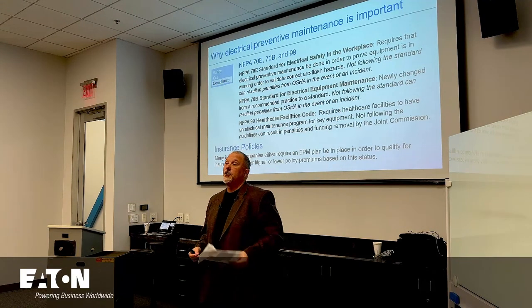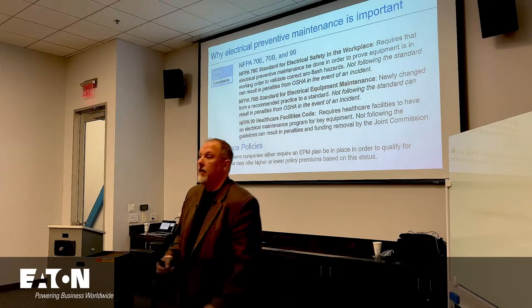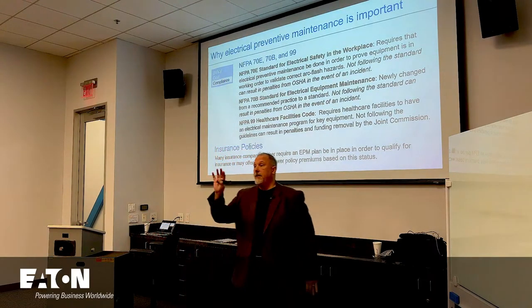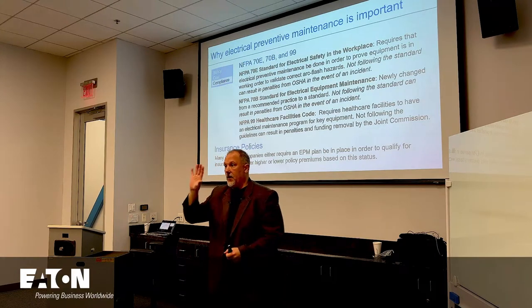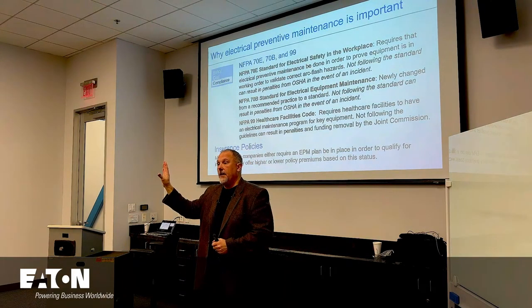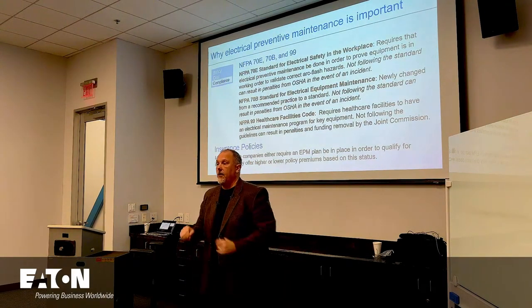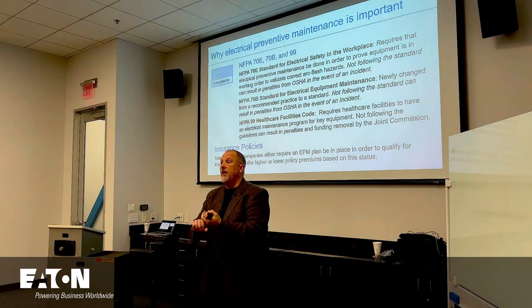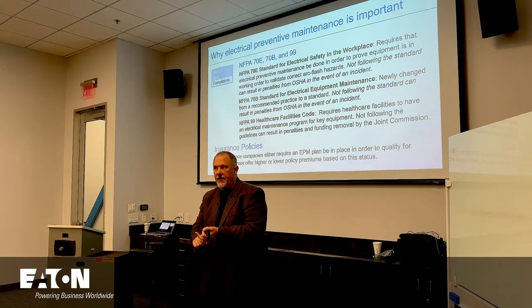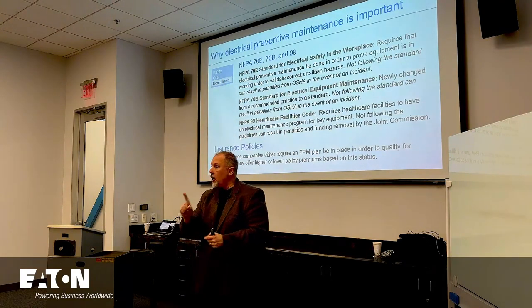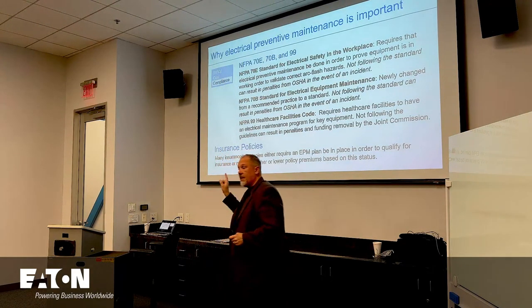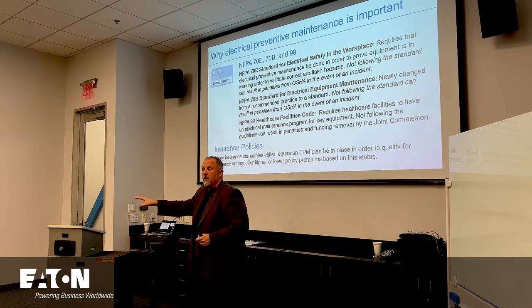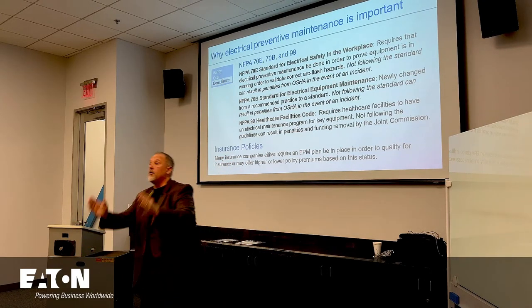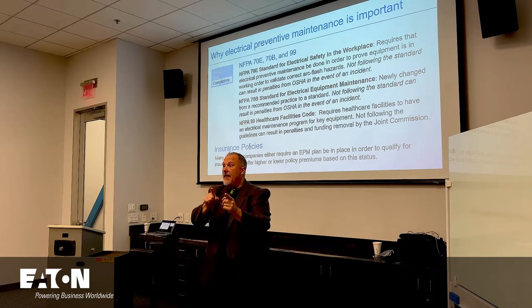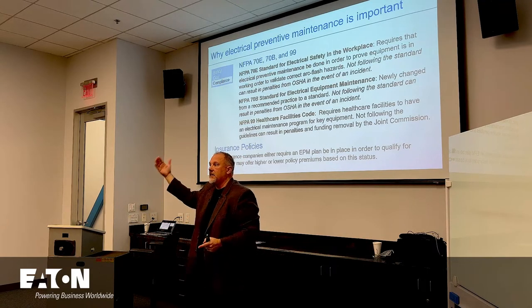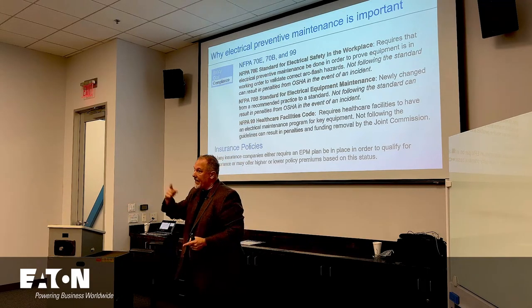So what you'd have to do is go to OSHA 1910 and 1926. In those, they'll bring up the laws around maintaining your power distribution system, your shock protection, and 70E. Remember, OSHA cannot enforce 70E or 70B. They will not enforce it. They'll enforce their own laws, and then use 70B and 70E to say this is what you should have been doing.